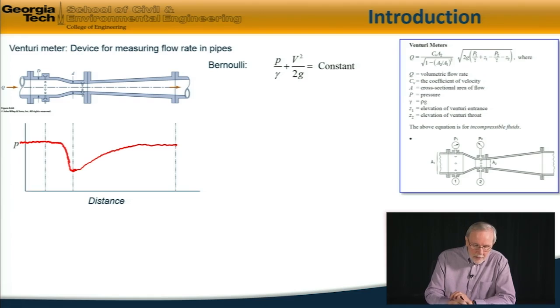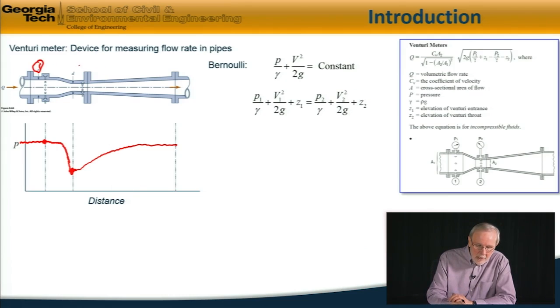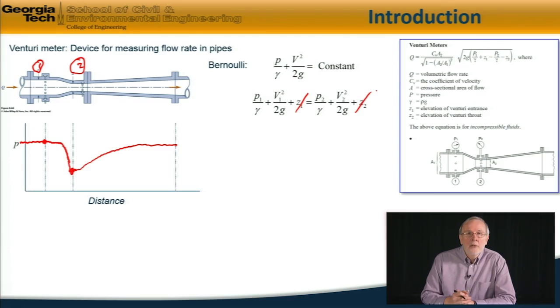Now we can relate the pressure difference at the throat here and the upstream pressure to the flow rate by continuing with the Bernoulli equation. So if I have station one upstream here and station two at the throat, we have the Bernoulli equation as shown. If the meter is horizontal, then the elevations Z1 and Z2 are the same, so they cancel out, leaving us with this equation.